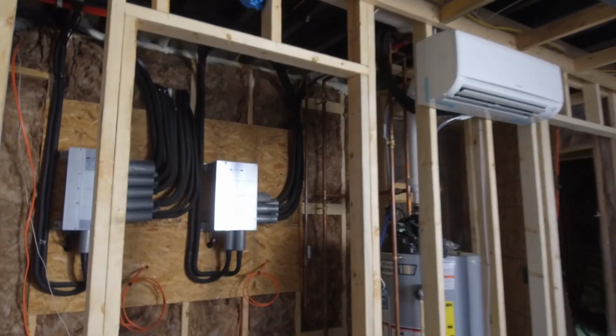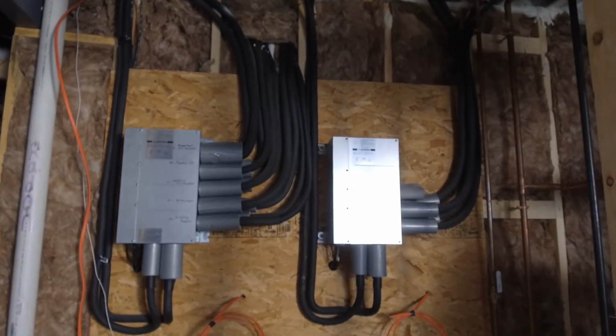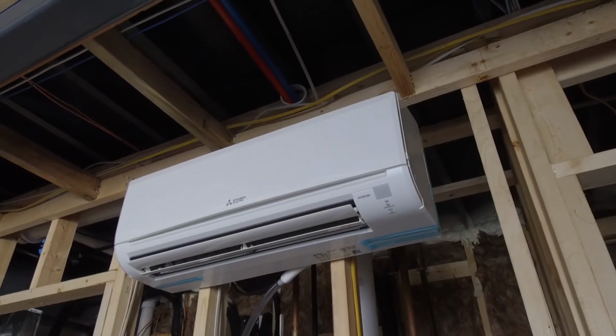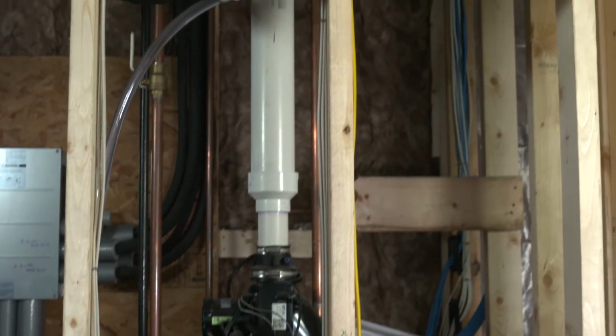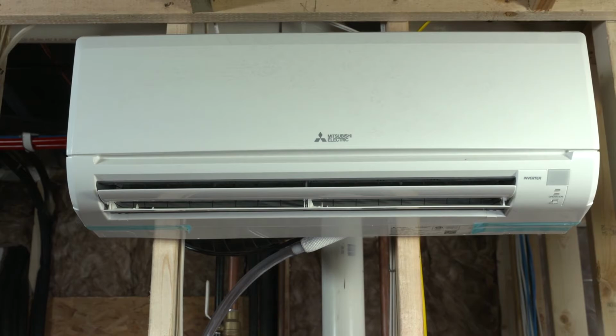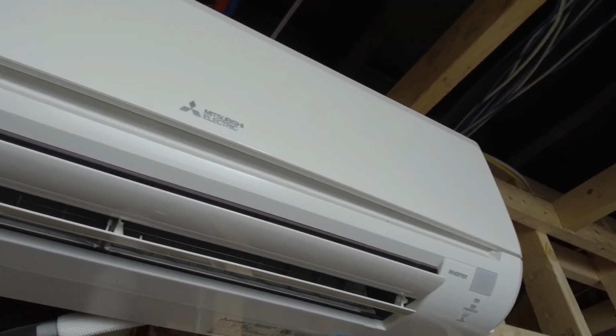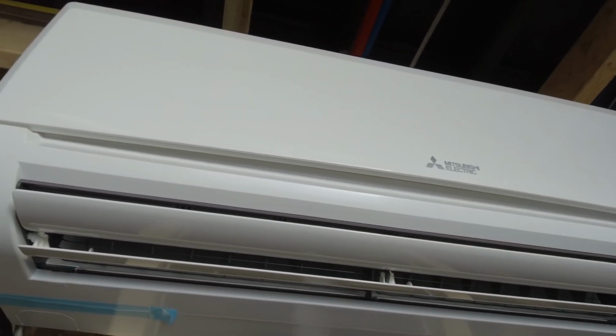All right, now a ductless system certainly is different from a traditional HVAC system. If I'm considering getting one, how do I know that it's worth the investment for a particular space? What factors should I be thinking about? So you'd want to be looking at a few different factors. Making sure that there's no way to condition that space with traditional ductwork. Looking at the electrical requirements, how you'd get the wiring run for the outdoor unit, and then how we're going to get that refrigerant line set from the indoor component to the outdoor unit. A lot of consideration needs to go into the clearance for the indoor unit. There's a certain amount of space around these heads where it needs to be able to circulate airflow properly. So making sure you physically have the space on the wall to put that head, or just the routing of the line set in general.